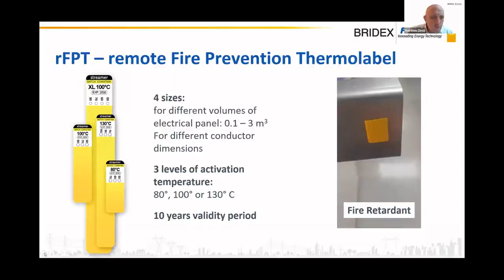So yes, I will just go back to the FPA. The question is about the presence of other gases inside the environment of the panel or the switchgear that could cause the FPA to trip, rather than the gas coming out of the stickers. So this is, let's say, not really a common problem, but it's a problem that occurred at the beginning when we were launching the solution.